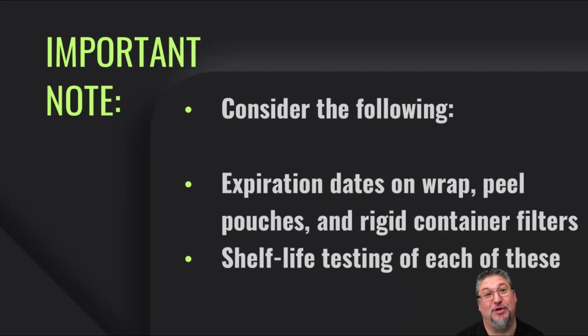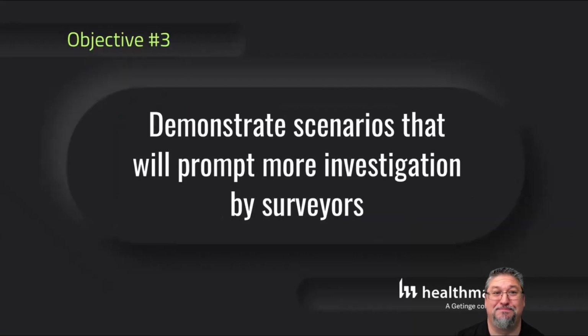Expiration dates on wrap, peel pouches, rigid container filters. A lot of those only have like a 6-month or 1 year expiration date on them. Then look at that shelf life testing and really start to see how long they can realistically stay on the shelf. And if you're going to go past that date, that's totally up to the facility if you want to go past what the manufacturer has tested for. But I would recommend you do a risk assessment and say, look, we're going to go to 2 years or 3 years beyond what the manufacturer says because we've done a risk assessment and here's the data we're using to justify it. Surveyors are good with that, but if you don't mention it at all, that's usually something that they're going to investigate more.